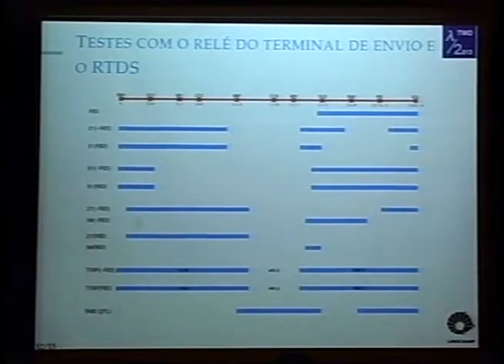Here we also have the performance of the under voltages without RID. It didn't change when we used RID. The under voltage device without RID works a little bit after the beginning of the line and also at the end of the line. The over voltage device also works in complement to the under voltage device, except in the middle of the line, because we created a gap between 0.8 pu and 1.2 pu. And then we have the under voltage device with RID, and it does not work in the final segment of the line. It blocks the under voltages, and the same thing happens with over voltages.